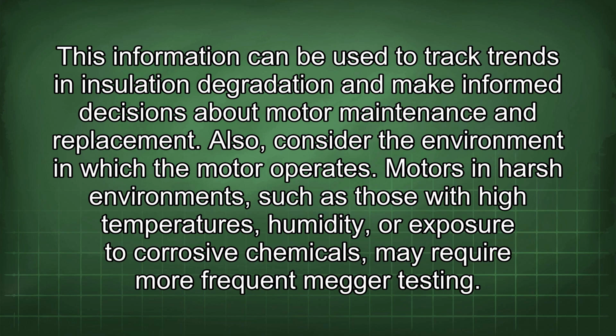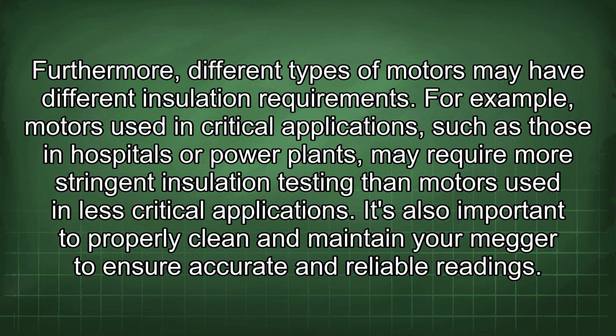maintenance and replacement. Also, consider the environment in which the motor operates. Motors in harsh environments, such as those with high temperatures, humidity, or exposure to corrosive chemicals, may require more frequent Megger testing. Furthermore, different types of motors may have different insulation requirements. For example, motors used in critical applications, such as those in hospitals or power plants, may require more stringent insulation testing than motors used in less critical applications.